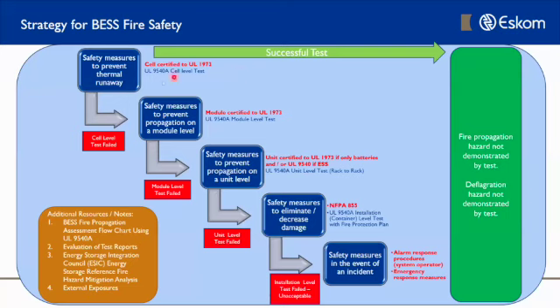The additional thing we looked at was UL 9540A, where they actually force a cell into thermal runaway and look at the fire propagation hazard and the off-gas—the gas that comes off the battery when it burns, depending on the chemistry. Is it toxic? How toxic? What are the explosion considerations we must take into account when designing the system?